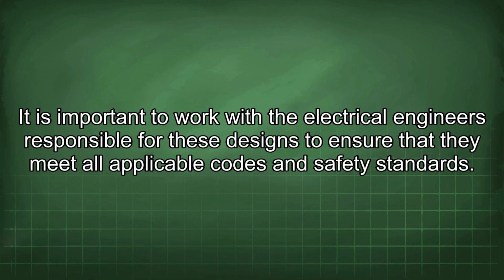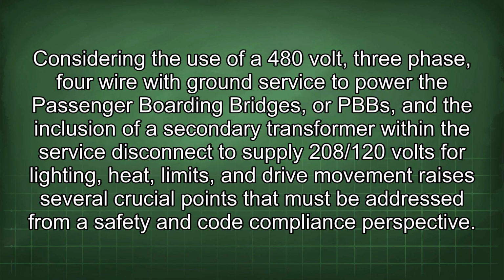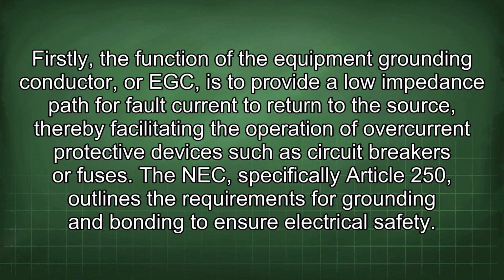Considering the use of a 480-volt, 3-phase, 4-wire with ground service to power the passenger boarding bridges, or PBBs, and the inclusion of a secondary transformer within the service disconnect to supply 208/120 volts for lighting, heat, limits, and drive movement raises several crucial points that must be addressed from a safety and code compliance perspective. Firstly, the function of the equipment grounding conductor, or EGC, is to provide a low impedance path for fault current to return to the source, thereby facilitating the operation of overcurrent protective devices such as circuit breakers or fuses. The NEC, specifically Article 250, outlines the requirements for grounding and bonding to ensure electrical safety.